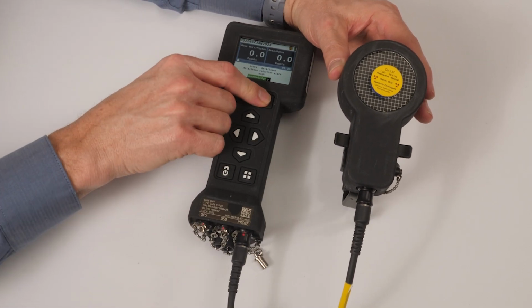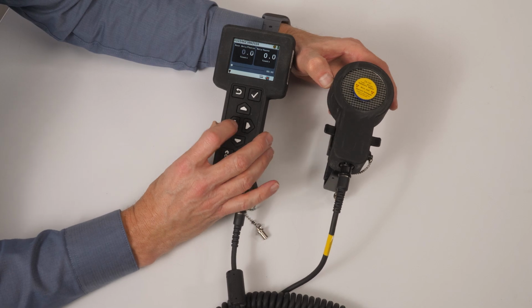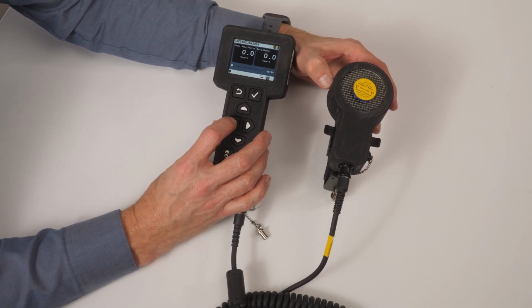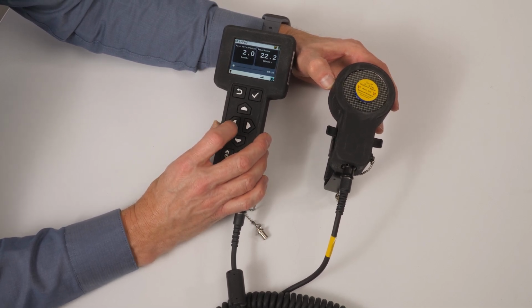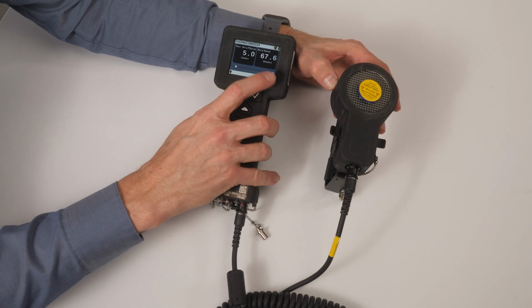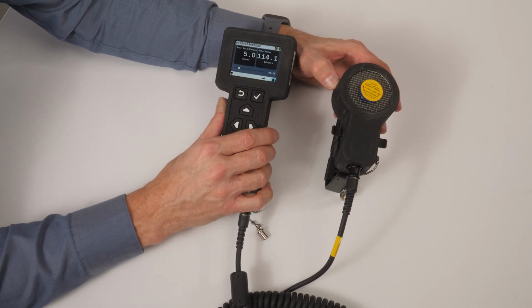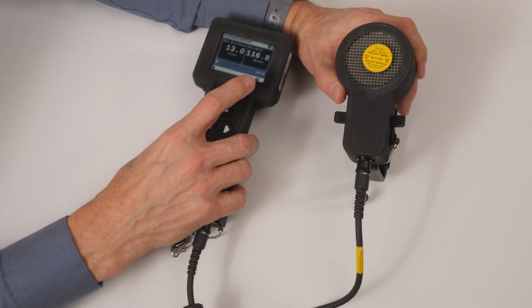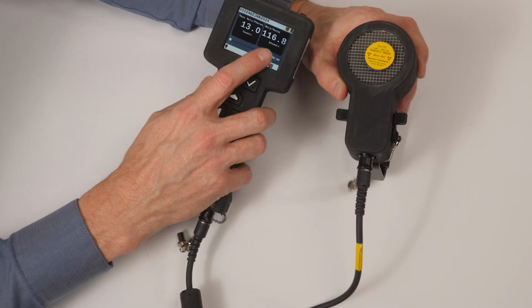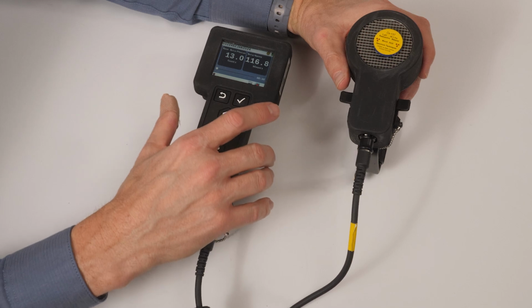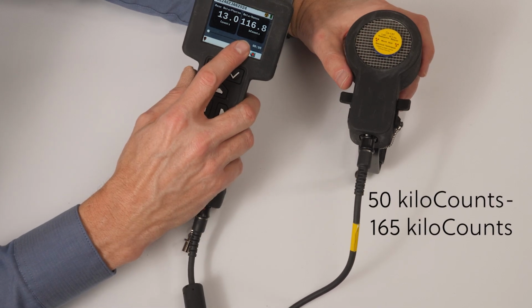Acknowledge any alarms by pressing the enter key. Press the left arrow key to start the scalar count. Hold the check source in place for the duration of the scalar reading, which is a countdown of 30 seconds. Note the number of counts reported in the beta-gamma radiation reading panel at the end of the 30-second time. Verify that that reading value falls within the range of 50 kilocounts to 165 kilocounts.